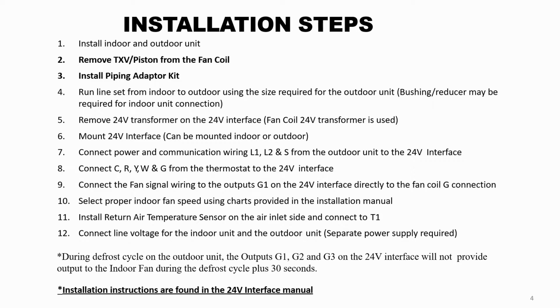The next step is to run the power and communication wiring L1, L2, and S from the outdoor unit to the 24-volt interface connection. The next step is to connect C, R, Y, W, and G from the thermostat to the 24-volt interface. After that's complete, you want to connect the fan signal wiring to the output G1 on the 24-volt interface and run that directly to the fan coil G connection.